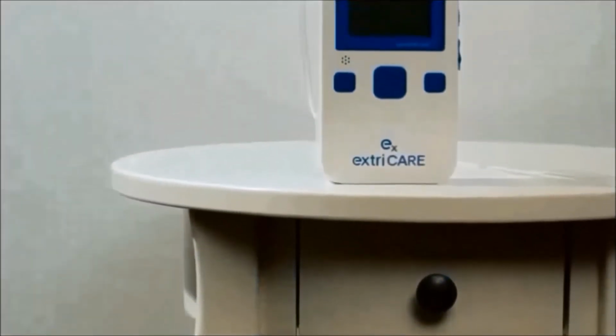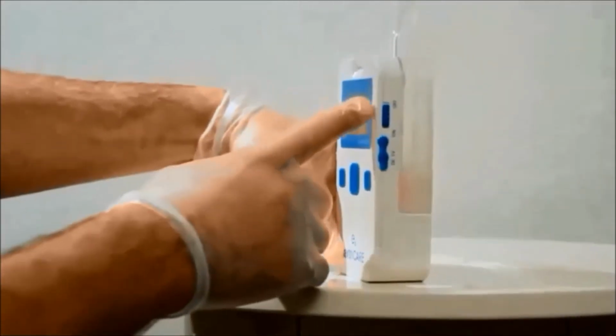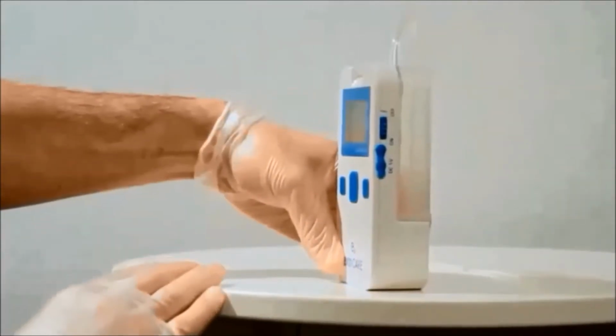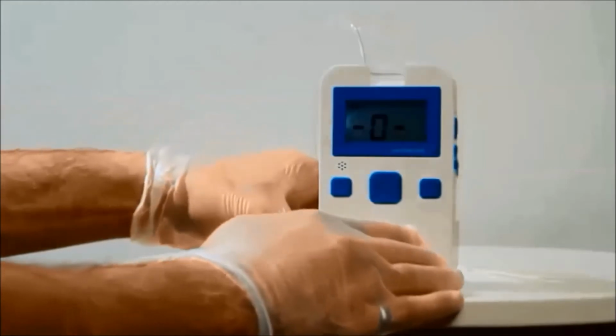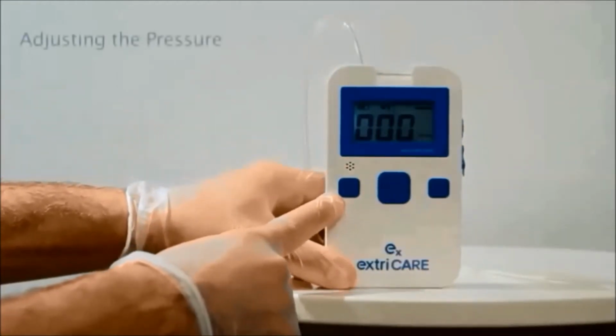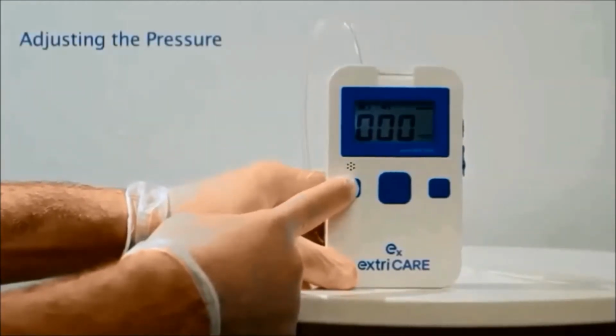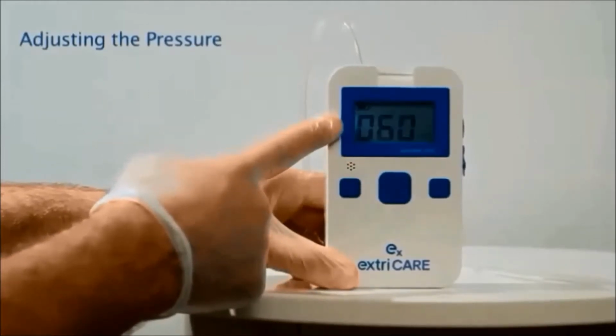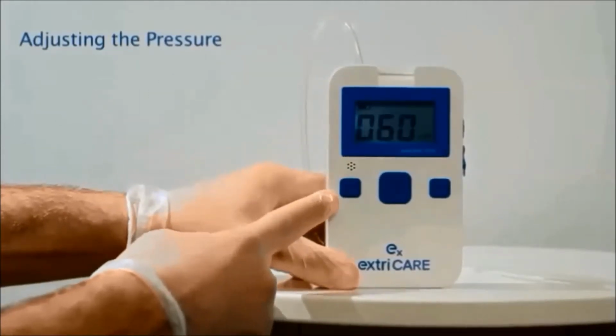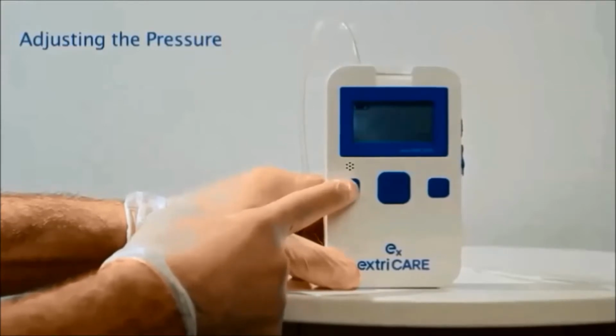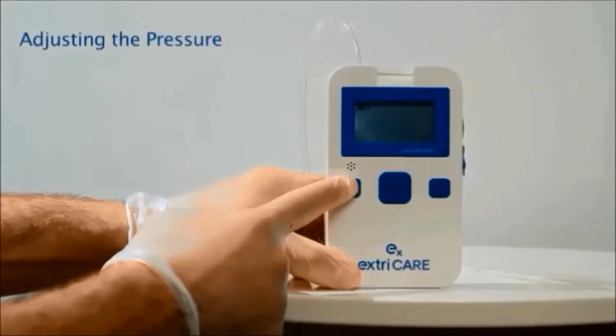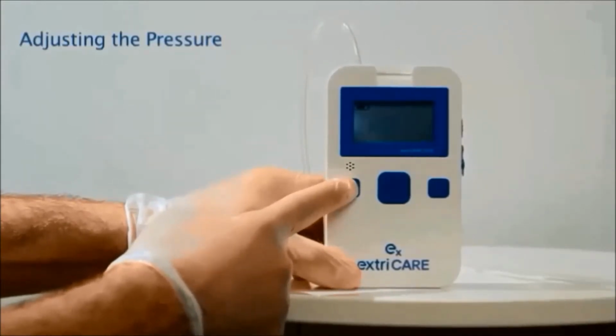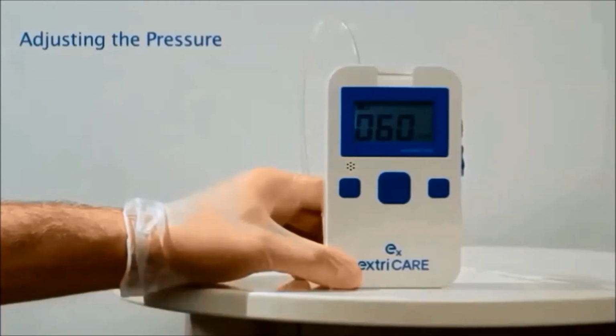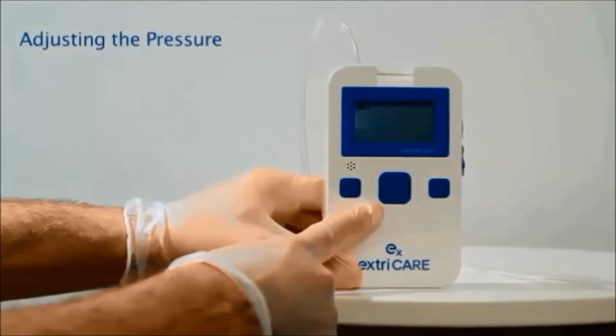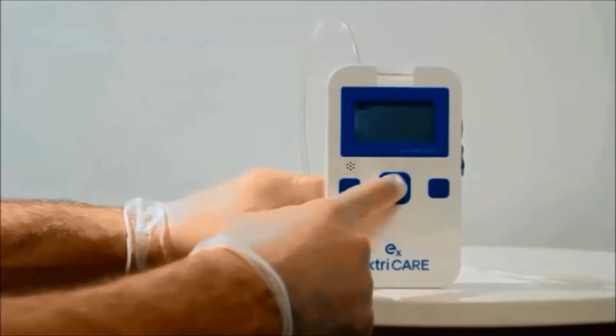To use the pump, push the on-off switch to the on position. To set the pressure, hold down the vac button until you hear a beep. You will see a blinking number. To adjust the pressure, press the vac button. The pressure can range from 40 millimeters of mercury to 140 millimeters of mercury. Once it cycles to the prescribed pressure, press the pump button to confirm.